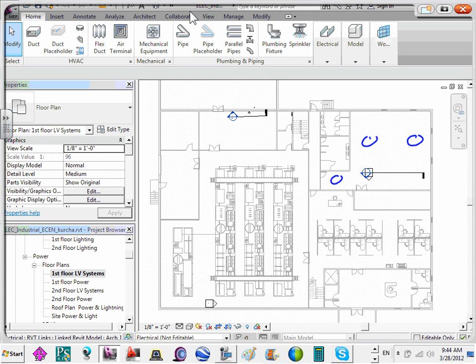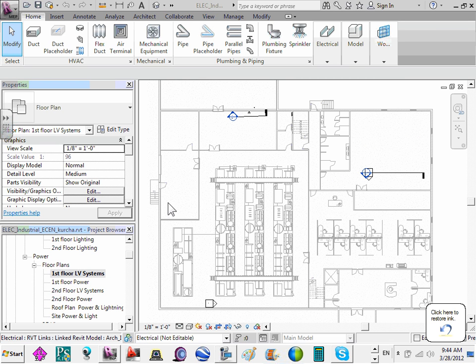Are you using these to augment or replace the fire alarms? It depends on what the owner wants. If this is a building that requires voice evacuation, fire alarm code states that you cannot use a paging system, because this is an unsupervised system, as your fire alarm notification. But you can put fire alarm speaker strobes in and you can page over the fire alarm speakers. That's one way you can reduce. So there's some double paging. Yeah, you can do live paging through a remote mic, or there's a telephone, you dial in and then you can page different areas. And that all depends on the system that's going in there.